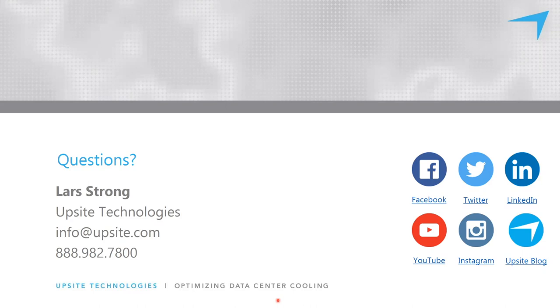IT equipment. And I mean all of it, every U space in the computer room. And that's most effectively done with an infrared camera. Then reduce the intake temperatures of all the hotspots, make everything as even and as cool as possible by improving airflow management and rearranging supply tiles. And then you can begin the process of reducing fan speeds and increasing temperature set points as much as possible. I think that's the best answer, but if there's something specific, of course, happy to go into that in more detail. Great, thank you, Lars.